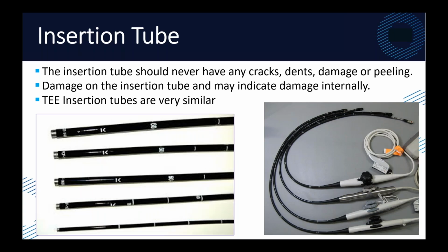When we talk about insertion tubes, on the left is a picture of various size insertion tubes that you can have in endoscopes. On the right, a variety of TEE probes from different manufacturers, and you can see all the insertion tubes leading up to their ends there. So we do always want to inspect TEE probes for damage to insertion tubes. Want to keep an eye on that. It is not the number one thing we see, but we do see it.